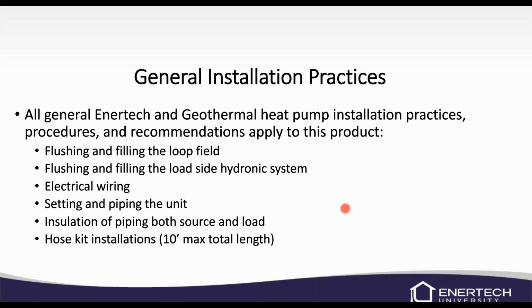And again, we still have that rule that the hose kit to the flow center is a 10-foot max total length. So 5 foot one way, 5 foot the other. So 5 foot there, 5 foot back. So all the general installations still apply to this unit. It's variable speed, but it doesn't change the fact that it's a geothermal unit. So we still have to flush it, put antifreeze in the system, and all that kind of good thing.